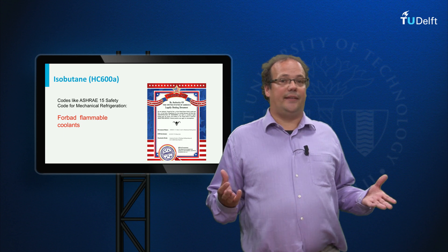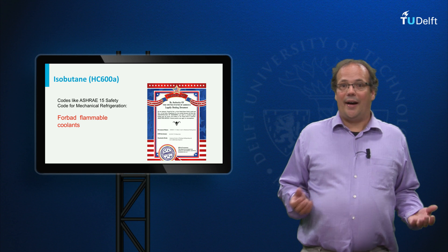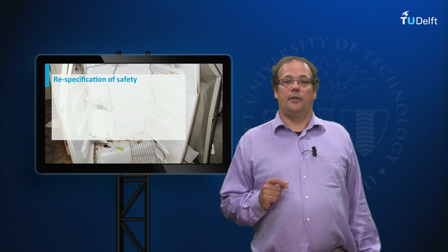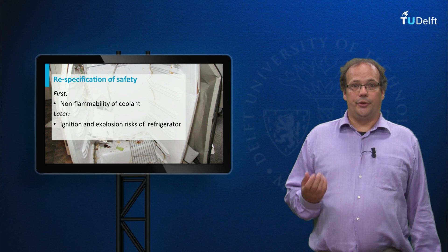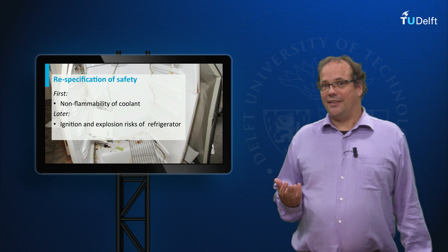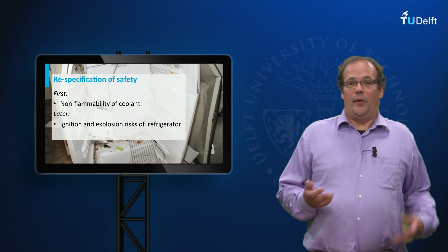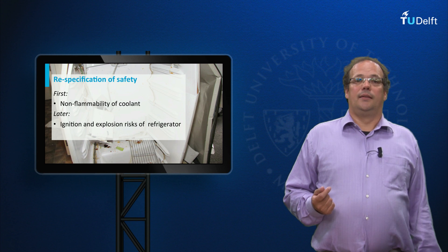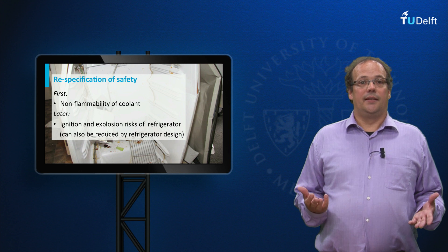In fact, the existing technical codes at the time banned the use of flammable coolants. Still, isobutane/propane came to be accepted. To understand why, we have to look at the interpretation of the value of safety. Safety was first understood as the non-flammability of coolants. But later, it was understood in terms of ignition and explosion risk within a fridge. Flammable coolant now turned out to not be as dangerous as generally thought, partly because fridges contained only a very small amount of coolant — when the original standards were formulated, fridges still contained much more coolant because they were less efficient. Moreover, it appeared to be possible to diminish the ignition risk by clever refrigerator design.